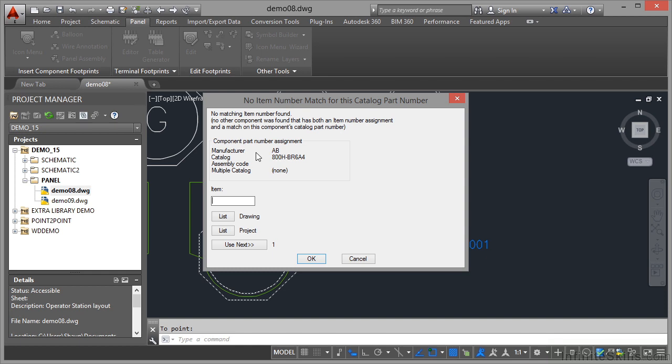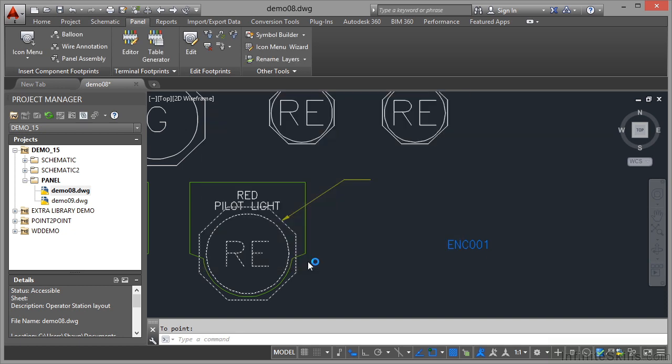It will prompt you now for the information. It's picked up the manufacturer from the catalogue listing. We need to give the item a number. I can choose from a list from the drawing, from the project, or use the next number in the list. We know it's item number 8 from the table. I click OK and item number 8 goes straight in that balloon. That's how quick and easy it is to utilize the balloon function in AutoCAD Electrical.